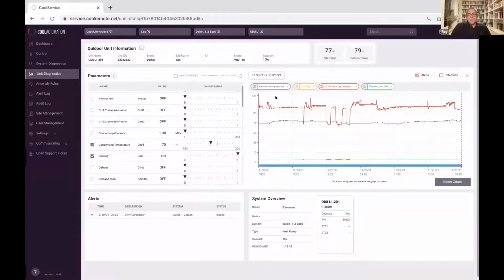By this anomaly, I automatically get the parameters that are interesting for troubleshooting it. Here I see the anomaly itself and the details of when it happened. I can see the different parameters—the condensing temperature is 111, and the ambient temperature is 73. So the difference is quite high, and it's been there for quite some time.